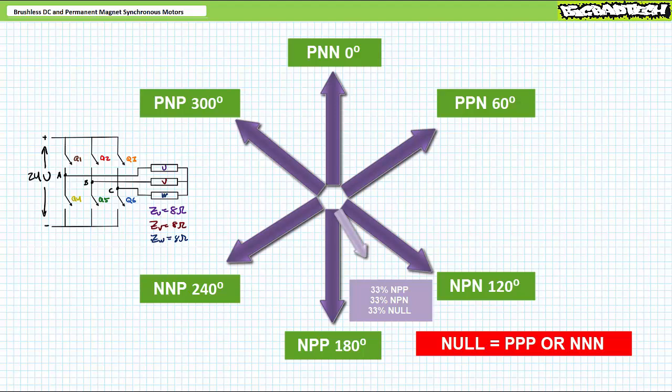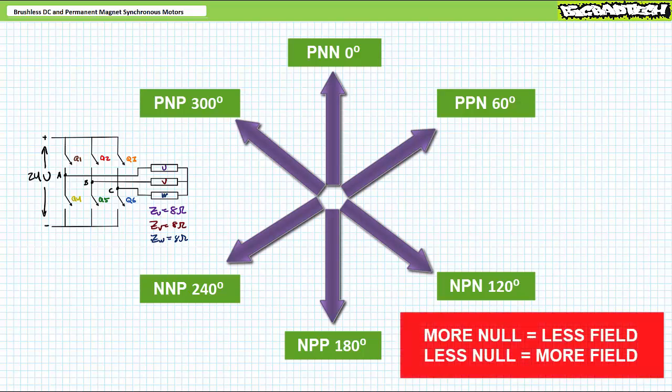This nothing or null state, depending upon implementation, might be known as PPP, where all the positive switches close, or NNN, where all the bottom switches are closed. By increasing the ratio of the null state in proportion to the two nearest vectors, we can decrease stator field strength. Conversely, by decreasing the ratio of the null state in proportion to the two nearest spatial vectors, we can increase stator field strength.